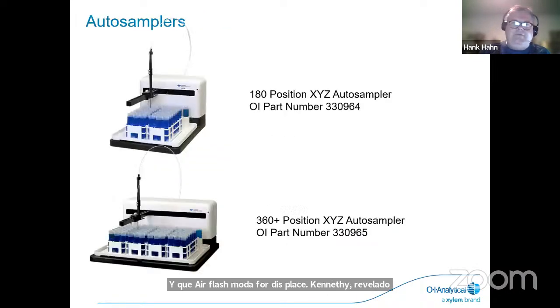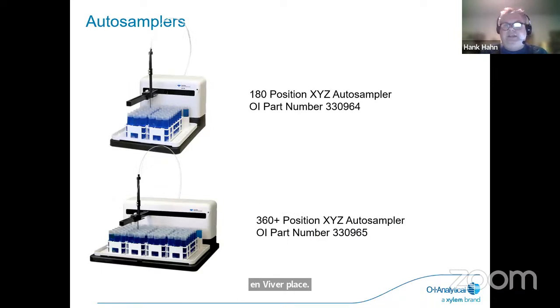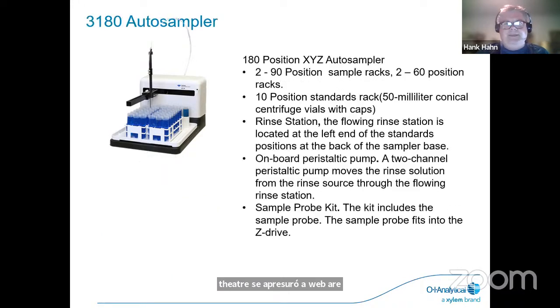We have a choice of autosamplers. We have a 180 position and we have a 360 position. We use the Teledyne CETAC sampler with our instrument, as CETAC is well known within the industry for autosamplers. The typical one that we quote is the 180 position. You get two 90 position racks, or you can do 360 position. You've got 10 positions for standards. We have a rinse station. The instrument includes an onboard peristaltic pump, and you get the sample probe kit, and that includes everything for the probe and the XYZ drive.